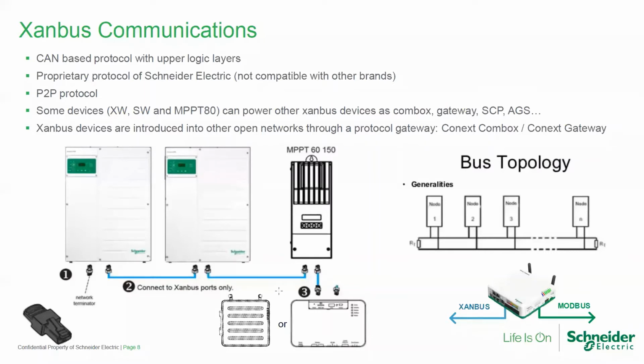We will see in a lot more detail what are the capabilities of the Conext Gateway as we do the demonstration of the remote monitoring and remote control. It is important to notice that while some devices will talk to each other on Xanbus, some other devices, as the grid-tied inverters, string inverters, will talk to the gateway on RS485 or Modbus TCP/IP.